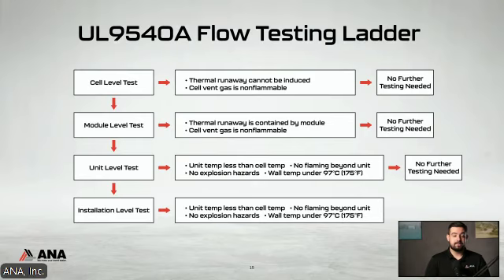Whatever it is, they will try to induce thermal runaway. If you're somehow able to pass at the cell level, meaning thermal runaway cannot be induced, and your cell does not vent any flammable gas or toxic gas such as hydrogen, you do not need to move on to the next level. So you would be able to stop there. Your 9540A testing would be deemed acceptable. This is rarely the case, as you cannot incorporate fire suppression methods into cell or module level products very easily. This typically happens at the unit level, where you're able to have active fire suppression in case of a fire. You're also able to have containment of the fire, if it were to occur, whether this could be a really thick steel enclosure or whatever. But the unit level is typically where people do stop.